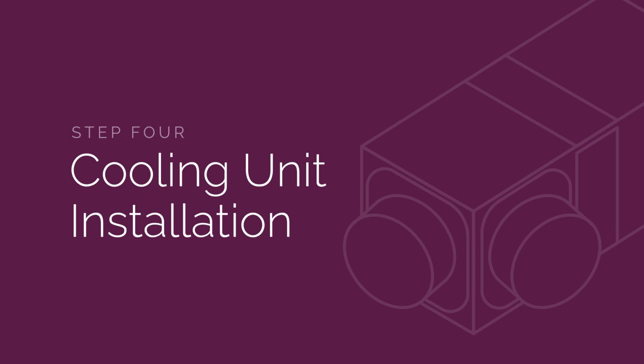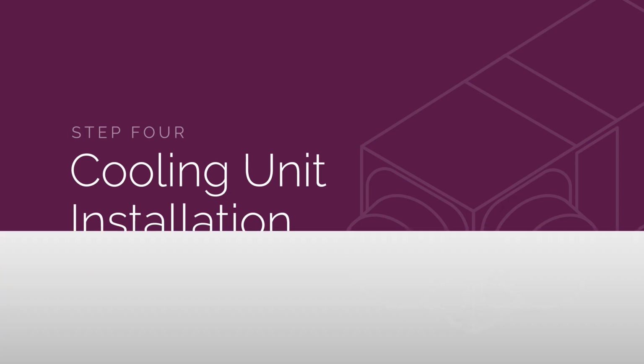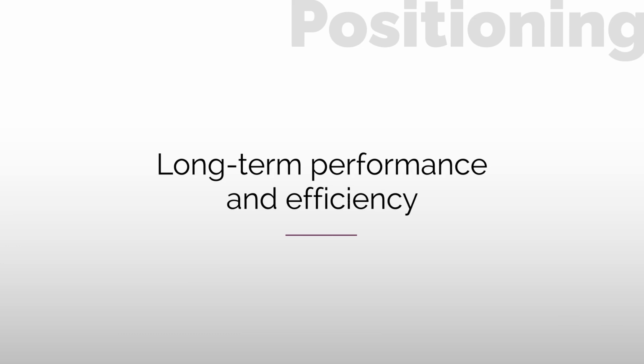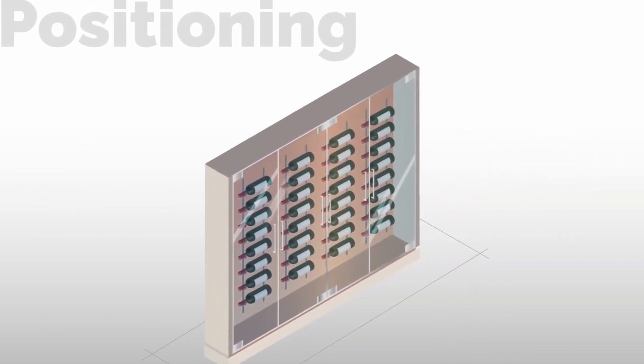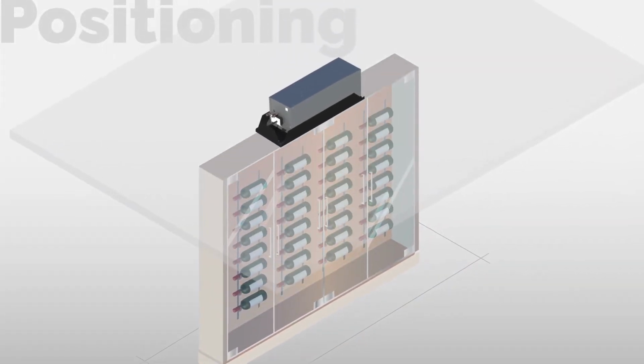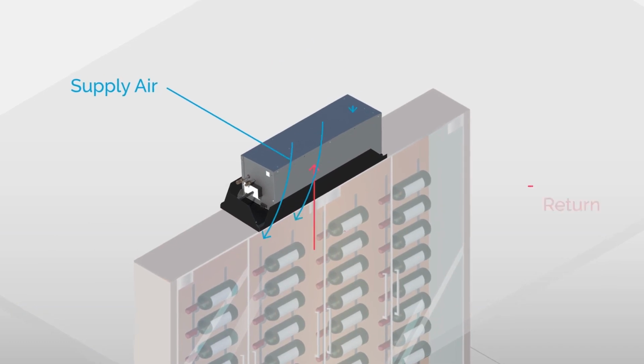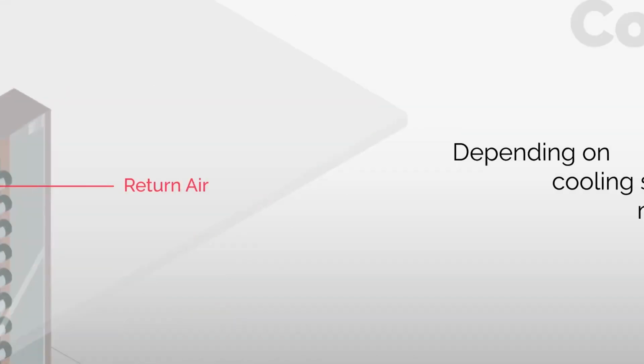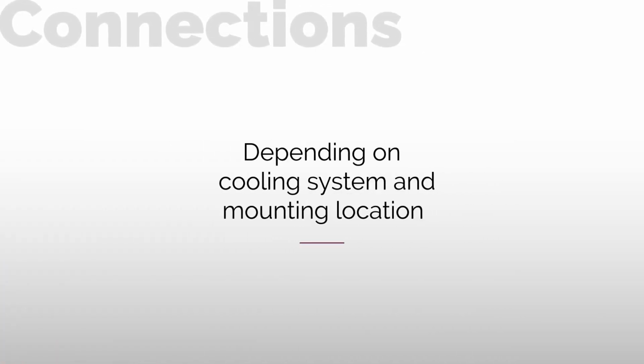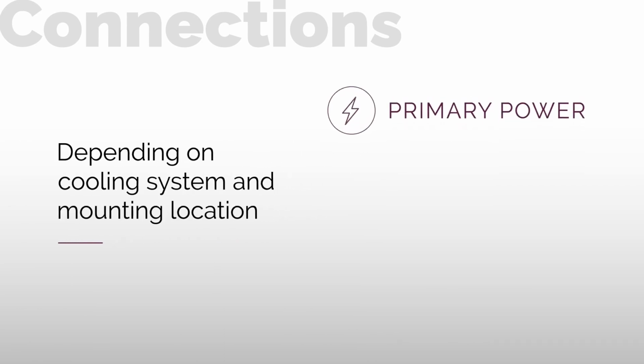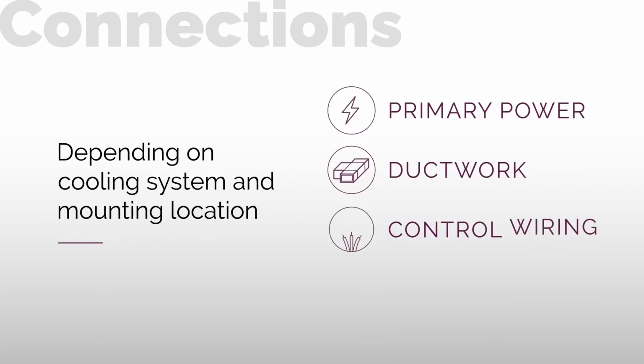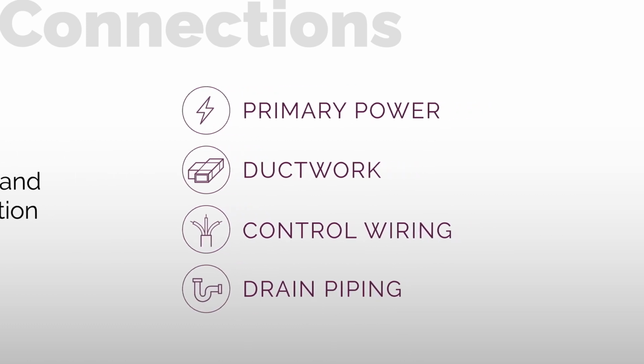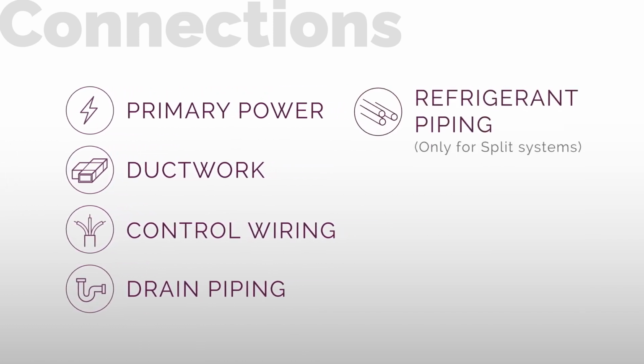Installing and mounting your cooling unit correctly is essential for long-term performance and efficiency. It all starts with positioning your unit in an unconfined location that allows for sufficient airflow. Depending on the type of cooling system and mounting location, you'll need connections for primary power, ductwork, control wiring, drain piping, and, for split systems, refrigerant piping.